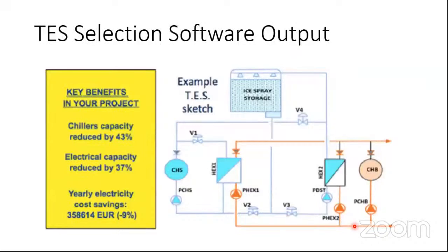This is in addition to the software output. I mean, this is also a part of it. It also generates a schematic depending upon your requirement, and it also suggests the chiller capacity reduced by how many percent, and the electrical capacity reduced by how many. So all this analysis it gives you. That's the kind of software output that is available with ice thermal storage manufacturers these days.